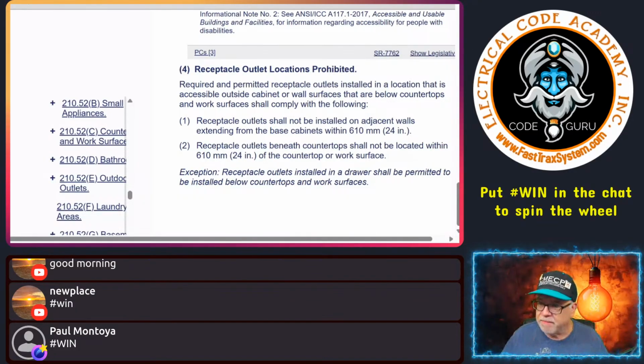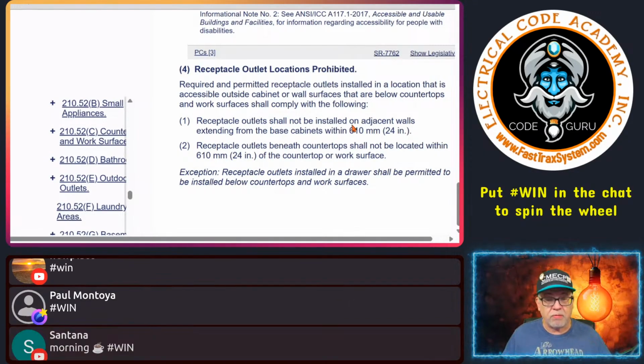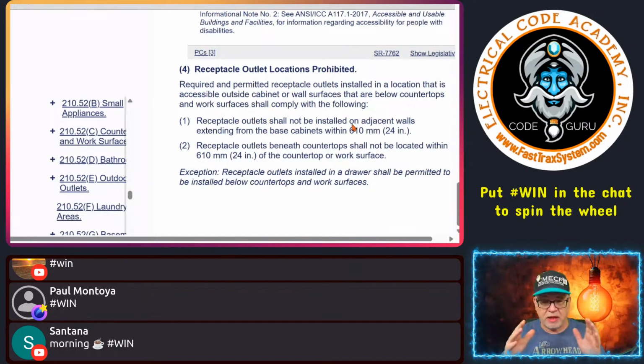But now it's saying, okay, look, number one, receptacle outlets shall not be installed on adjacent walls extending from the base cabinet within 24 inches. So if I have a peninsula, and y'all know how a peninsula works, right? You have the wall and you're perpendicular, you have a peninsula coming out. Well, if I have a receptacle in the wall that's continuing, let's say in the living room, that receptacle on the wall space, maybe down low at 18 inches or 16 inches, that cannot be within 24 inches of the base of the cabinet. Okay, so that's the first thing.